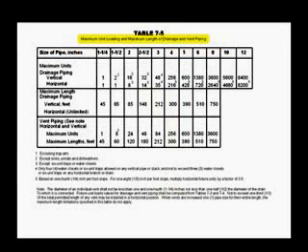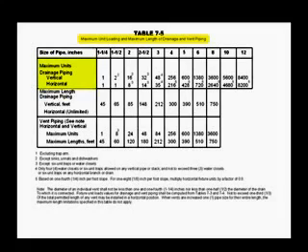Now refer to the maximum loading of drainage piping and maximum length of drainage and vent piping table 7-5 and under maximum units for both vertical and horizontal, move to the right to find a fixture unit number that will handle or include the total fixture units that the drain will serve and above that number it will indicate the minimum size of drain pipe required.